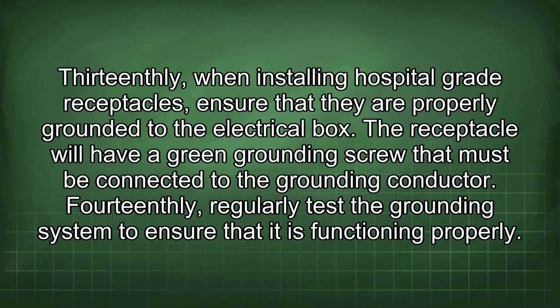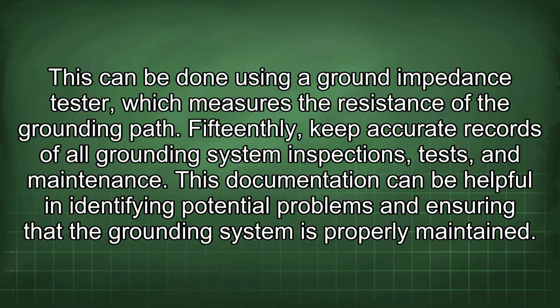Fourteenthly, regularly test the grounding system to ensure that it is functioning properly. This can be done using a ground impedance tester, which measures the resistance of the grounding path. Fifteenthly, keep accurate records of all grounding system inspections, tests, and maintenance. This documentation can be helpful in identifying potential problems and ensuring that the grounding system is properly maintained.